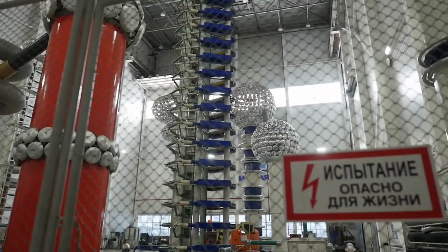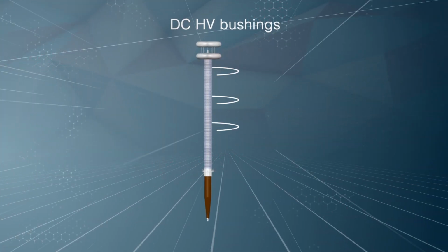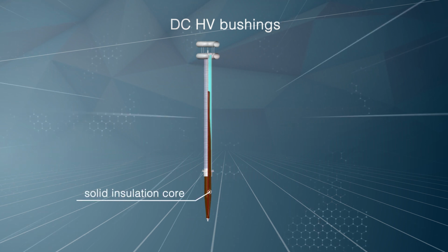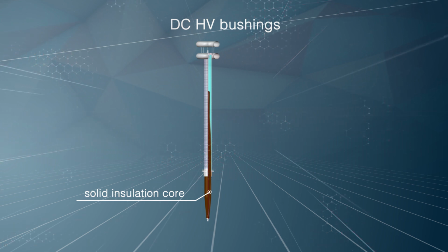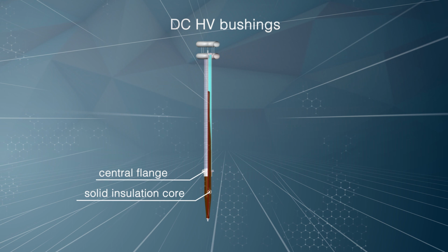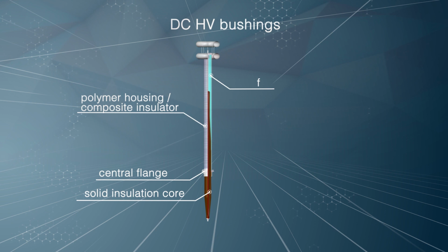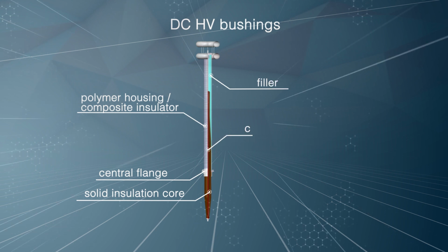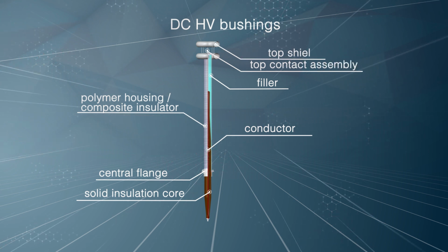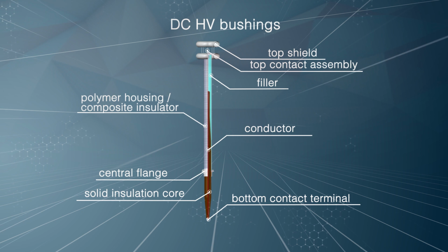The bushing consists of the following main elements: solid insulation core made by insulating paper winding on a central tube with subsequent saturation in epoxy compound, RIP insulation. Central flange fixed on the core and meant for fastening the bushing on a transformer. There is a polymer housing filled with gas on the bushing. There is a conductor all through the bushing, which has an airtight seal in the top and bottom parts of the bushing. The design office of Izolyator can customize type designs according to the features of the customer's equipment if necessary.